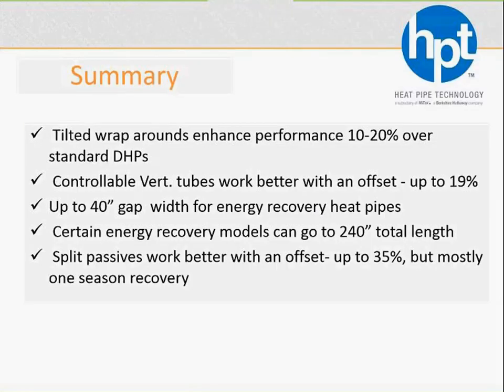So, in summary, a little tilt goes a long way with wraparound heat pipes. We get about 10 to 20% performance, depending on the length of the tube. The other approach, controllable verticals, works better with an offset by up to 19%. The gap in the energy recovery heat pipes now goes from 8 to 40 inches. Certain HRMs, or heat recovery modules, can now go from 200 to 240 inches, specifically the optimized HRMZ and the over-under. And with split passives, you can now extend the distance from 40 to 60 if level, and from 100 to 120 with an offset, and the performance with an offset increases by up to 35% for the season that you optimize for.